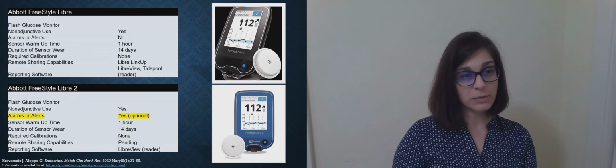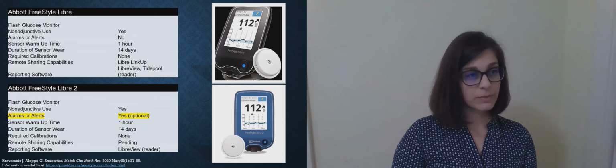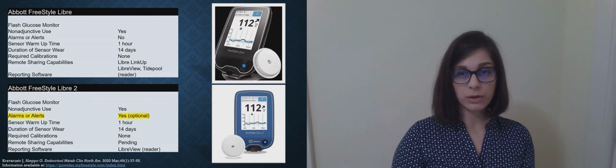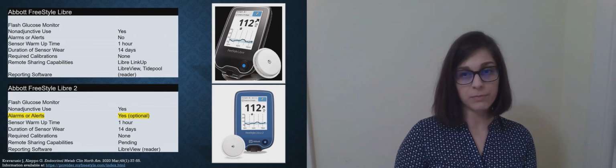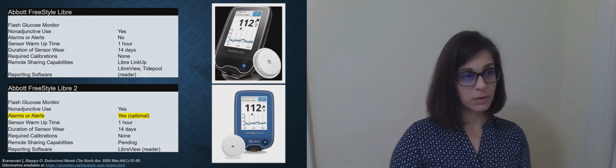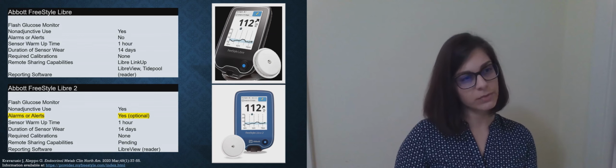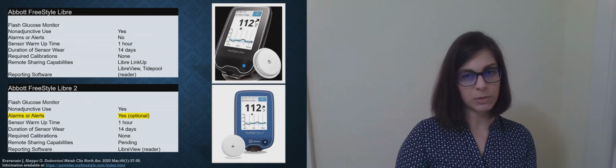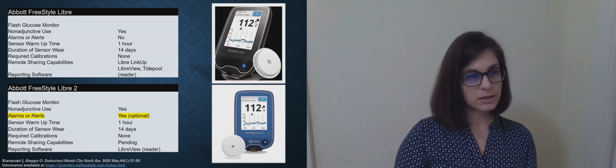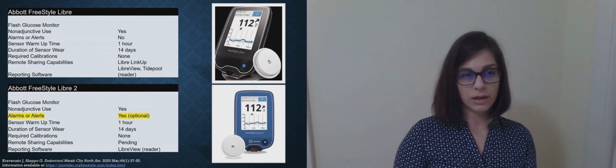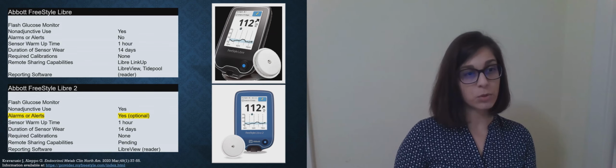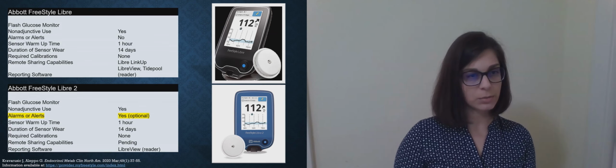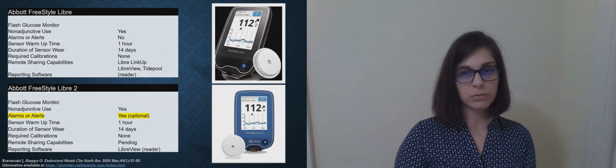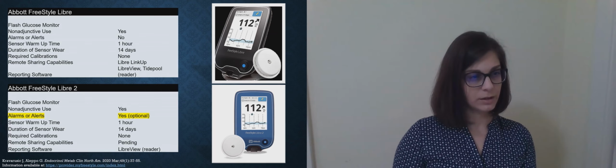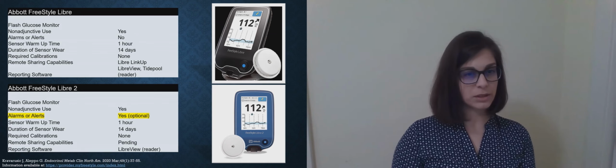Each system has a sensor warm-up time. The Libre is 1 hour, and a duration for sensor wear, which is 14 days. This device does not require calibrations with point-of-care finger stick glucose to maintain accuracy or reliability of the system. It is factory calibrated. And then there are also remote sharing capabilities, which we'll discuss a little bit later. But the systems can share real-time and also glucose data with clouds for reporting software. So here they have the Libre LinkUp, Libre View, and also Tidepool, which can pull together data. The Libre 2 is still pending some of these remote capabilities, but they are underway.